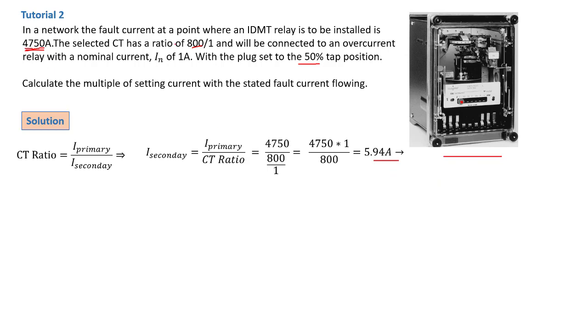We know that the formula for M, the multiple of setting current, is M equals I secondary over the setting current. And the setting current is equal to the nominal current here. It has a nominal current of 1 amp times the plug settings, which are set at 50%.